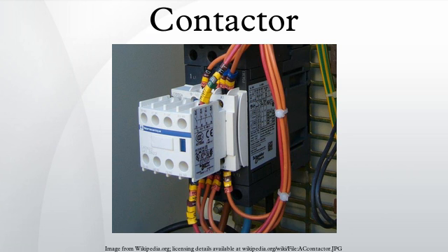Operating principle: unlike general-purpose relays, contactors are designed to be directly connected to high-current load devices. Relays tend to be of lower capacity and are usually designed for both normally closed and normally open applications. Devices switching more than 15 amperes or in circuits rated more than a few kilowatts are usually called contactors. Apart from optional auxiliary low-current contacts, contactors are almost exclusively fitted with normally open contacts. Unlike relays, contactors are designed with features to control and suppress the arc produced when interrupting heavy motor currents.